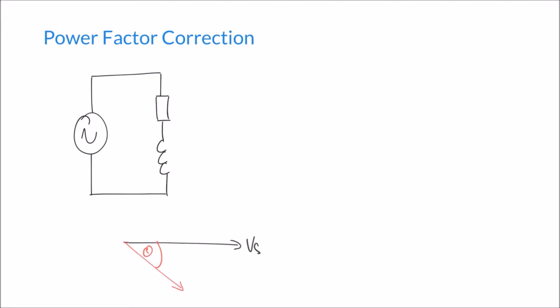This is a big problem because reactive power, which is dissipated by the inductor, is what we can think of as wasted power, whereas real power — the real component of power dissipated by a resistor — is what we can think of as useful power. This is a big problem in industry where we have large motors potentially dissipating a lot of reactive power as well as doing useful work with real power. One of the things we can do is correct for a lagging power factor by introducing a capacitor into the circuit.